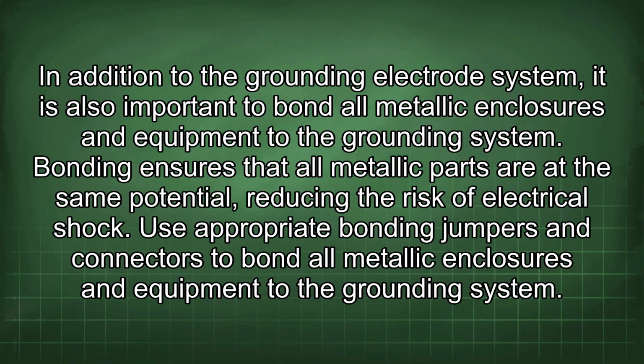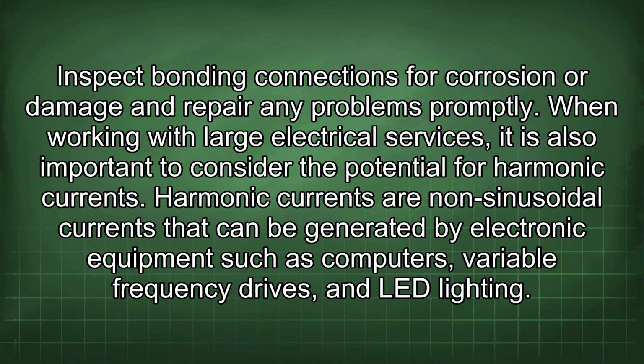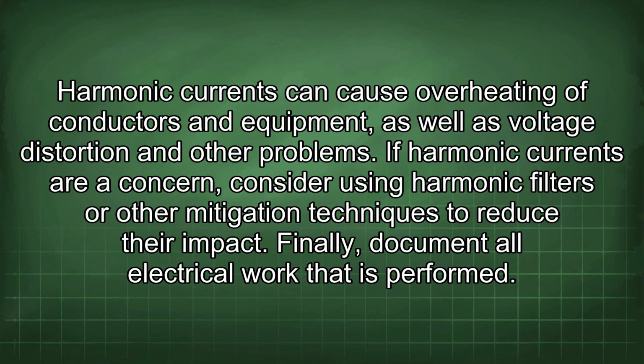Bonding ensures that all metallic parts are at the same potential, reducing the risk of electrical shock. Use appropriate bonding jumpers and connectors to bond all metallic enclosures and equipment to the grounding system. Inspect bonding connections for corrosion or damage and repair any problems promptly. When working with large electrical services, it is also important to consider the potential for harmonic currents. Harmonic currents are non-sinusoidal currents that can be generated by electronic equipment such as computers, variable frequency drives, and LED lighting. Harmonic currents can cause overheating of conductors and equipment, as well as voltage distortion and other problems. If harmonic currents are a concern, consider using harmonic filters or other mitigation techniques to reduce their impact.